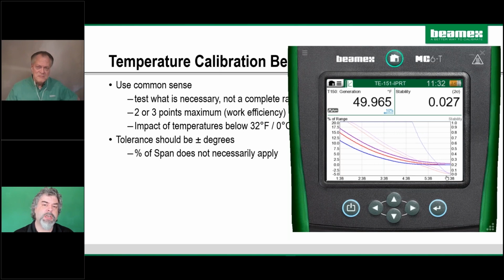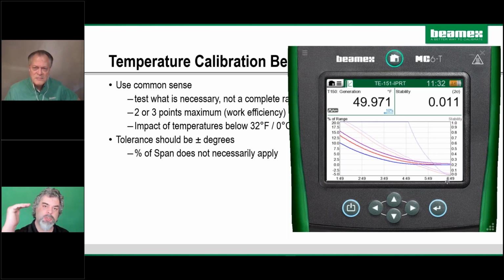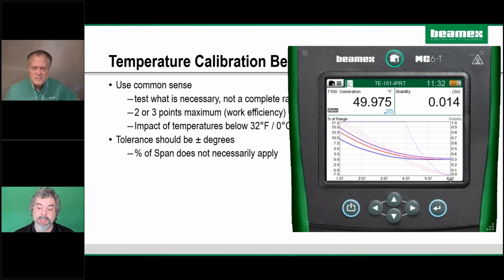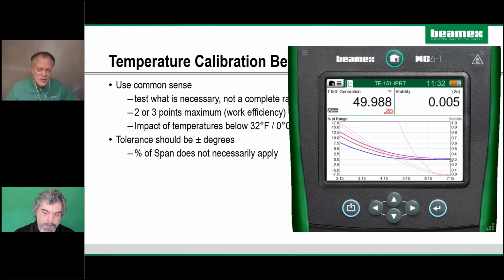Yeah, go ahead. So one thing, as you mentioned, this stability, I always think of it as a confidence level. It means that you don't have to worry about a certain time delay. Usually a temperature block will hit a certain temperature and it'll acknowledge it, it'll beep, and you have to put in a settling delay, maybe 3 minutes, 30 seconds, something like that. And so this means you don't have to do that, right? Exactly. And look how close it is, but there's still, this is 0%, but it just now recorded.